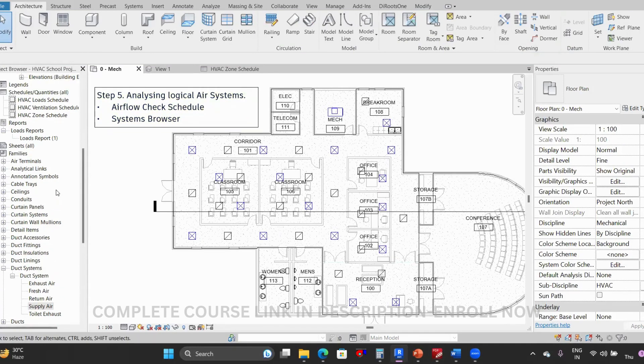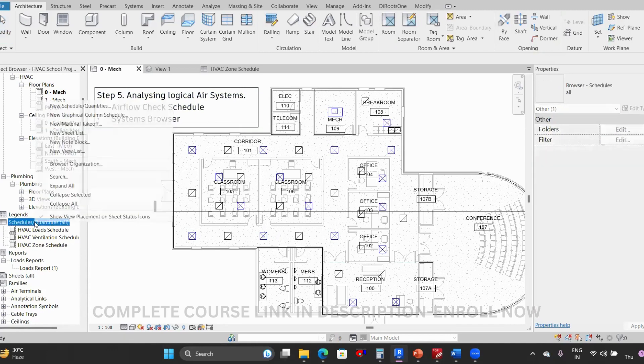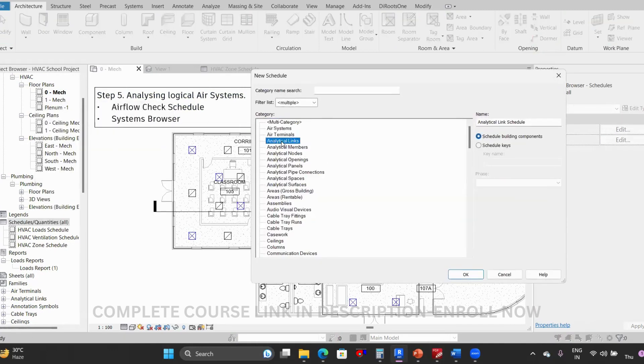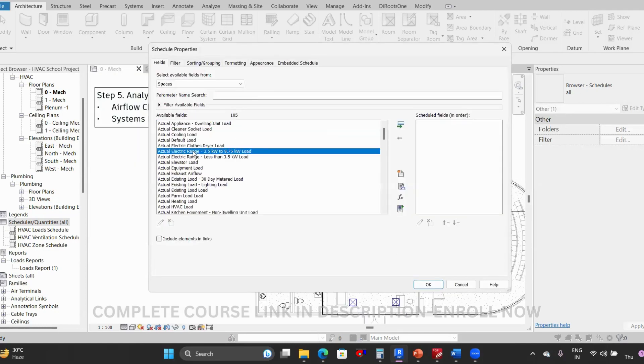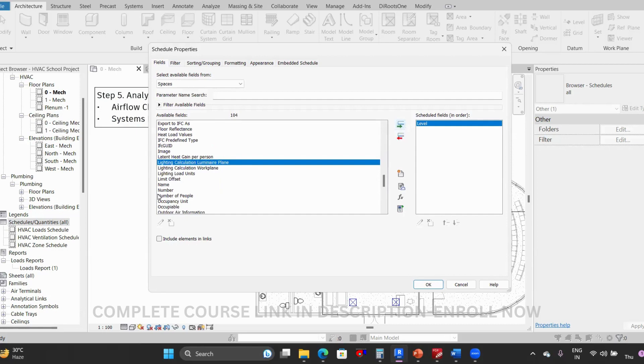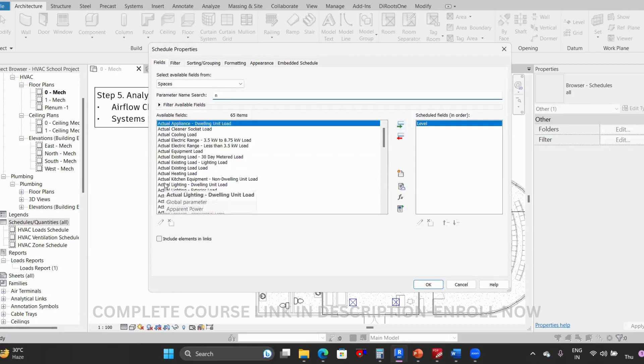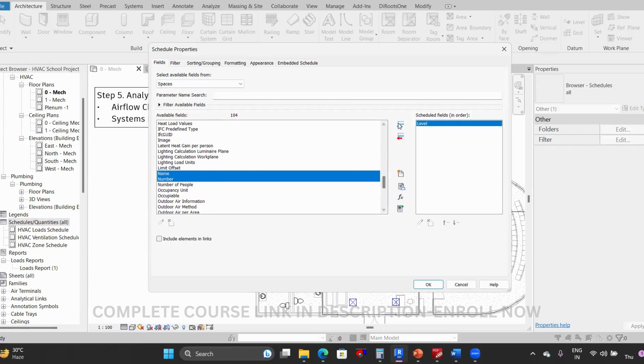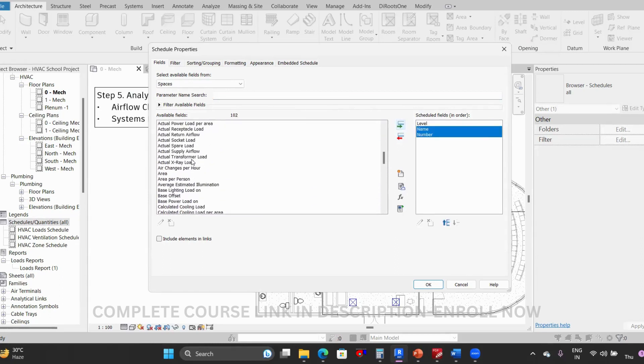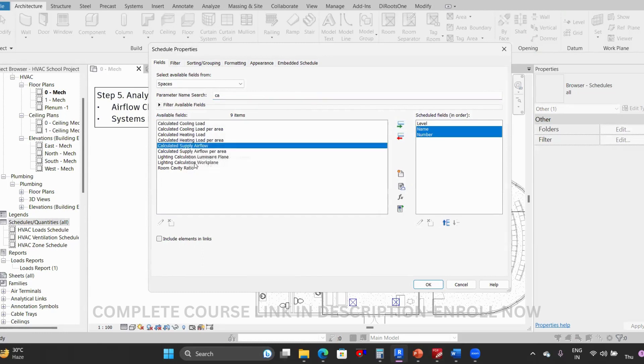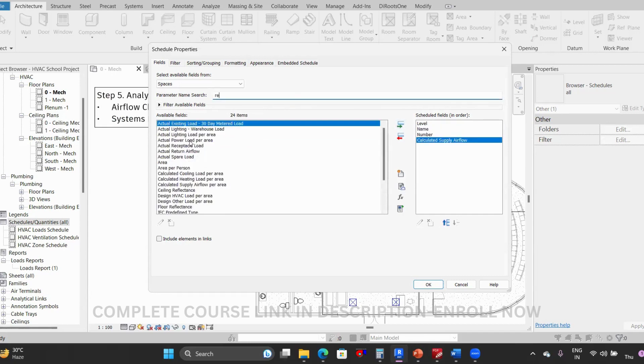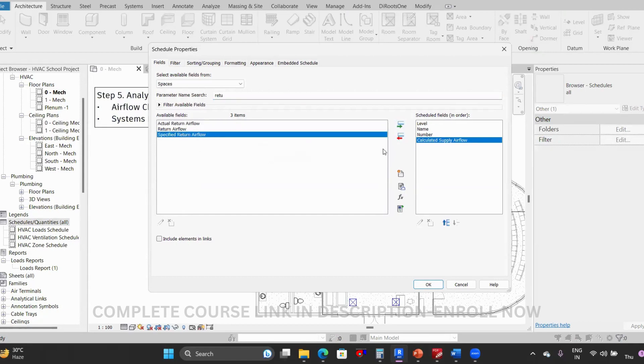To create the airflow check schedule, go to the Schedules tab, click on New Schedule, type 'S', select Spaces, and click OK. Here you can add the level, name, and number — space name and space number. Then we need to select calculated airflow, calculated supply airflow, and then the return airflow.